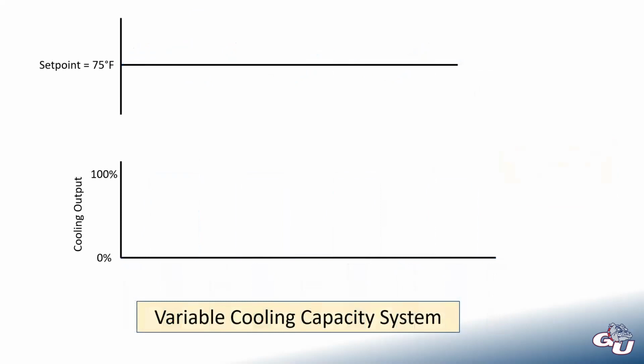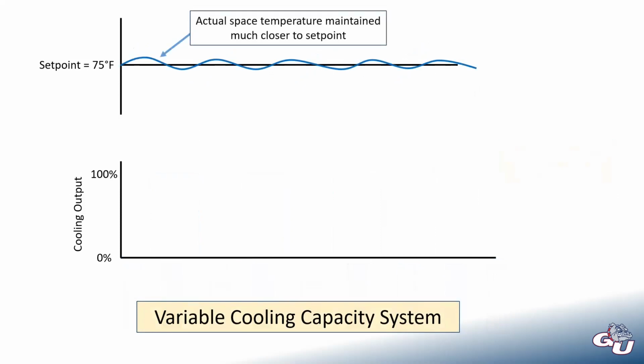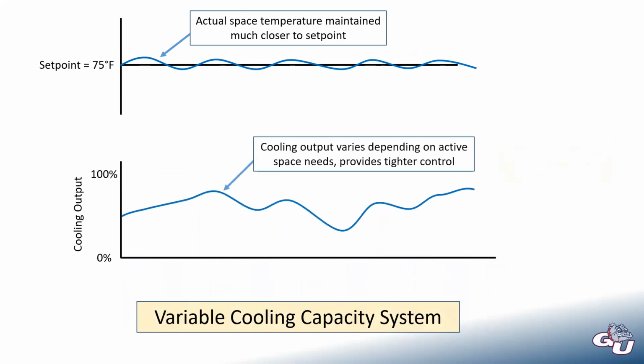Now, to contrast this, a system that has variable cooling capacity, you're going to get a much tighter band, or a tighter oscillation range, that's going to be much closer to where you want to be. You still don't get that perfect flat line. I mean, no system can provide that level of comfort, but the cooling output can go anywhere from 0 to 100% depending on what that space needs.